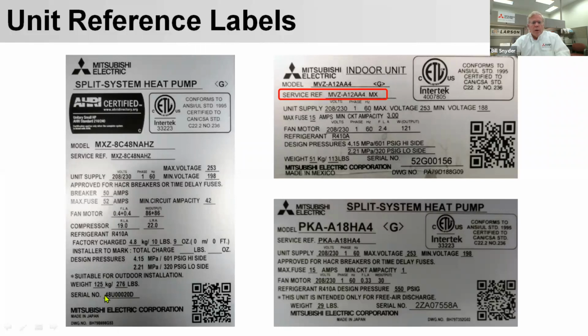Serial numbers are way down here on the bottom on their labels. We typically would look at model number and serial number on most of the American-made product that we look at, but in Mitsubishi, it's model number, service reference number, and then towards the bottom is the serial number. When you're calling in for technical support or parts, we need the service reference number and the serial number when you call in. You'll also notice the label has a QR reader.